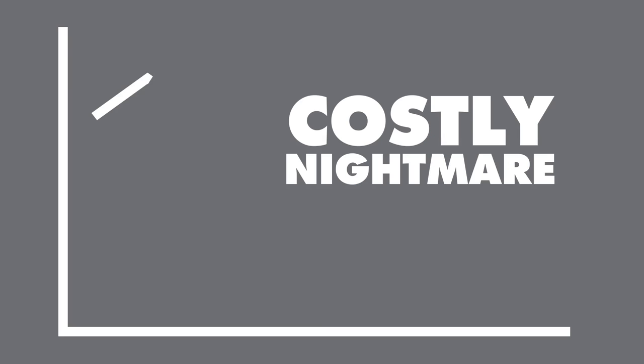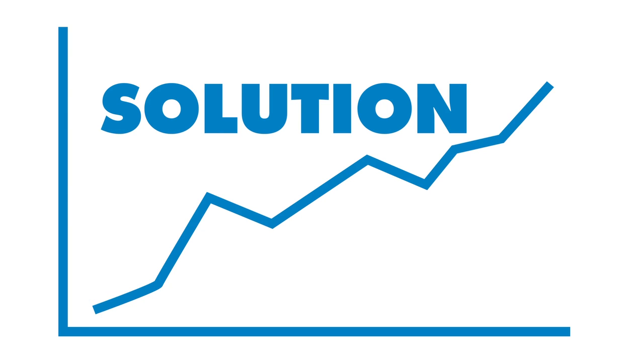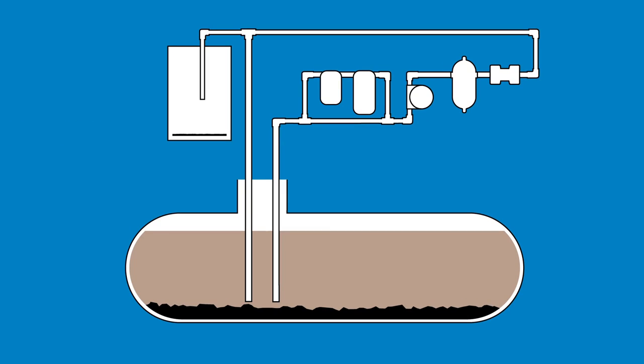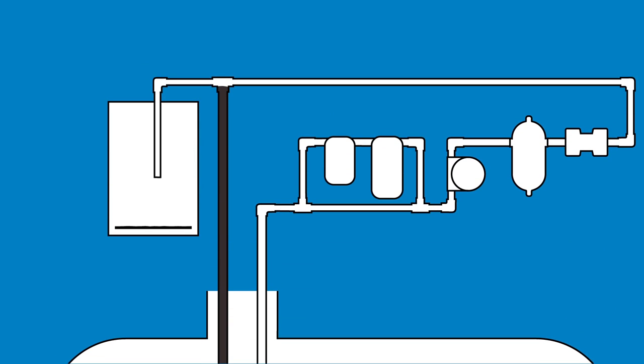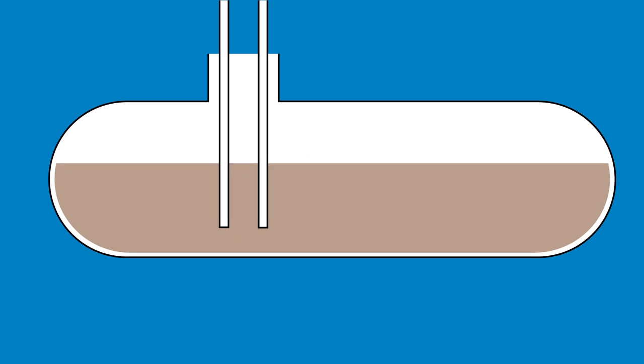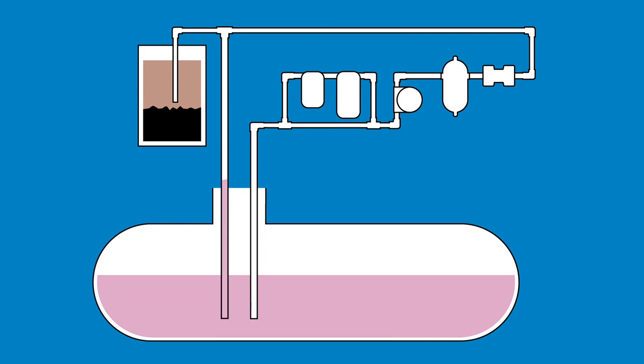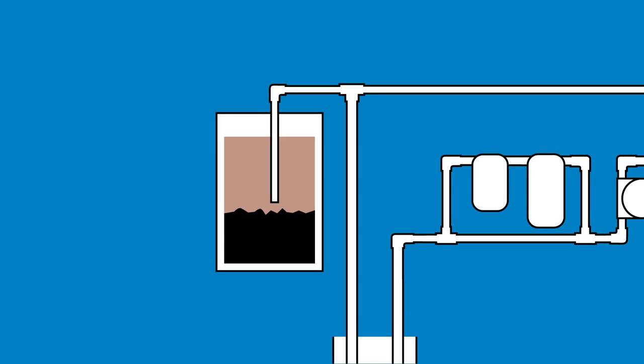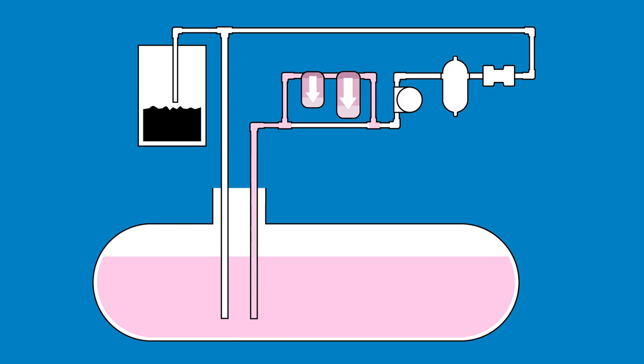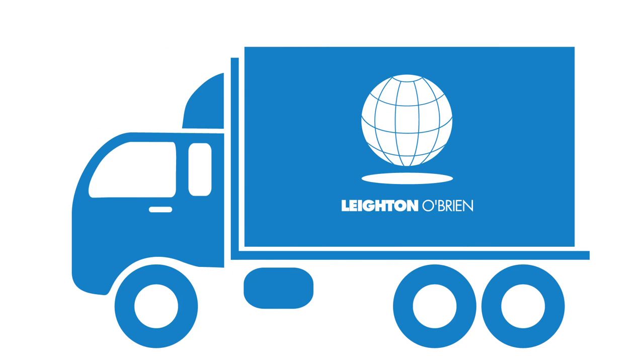Problems with dirty tanks and fuel quality can be a costly nightmare for your business. Leighton O'Brien provides a comprehensive solution for cleaning tanks and restoring fuel quality via a three-stage process. First, we remove water, sediment, and rust by traversing 100% of the tank floor and store this waste material in a settlement tank. The fuel is then circulated through clear hoses in a multi-faceted process including coalescing, fuel conditioning, and filtering, which removes emulsified water and small particulate matter down to 2 micron size. Finally, the remaining fuel in the holding tank is drawn off the top, treated, and returned to the tank — meaning only waste is removed and all your fuel is returned. Most tank systems can be cleaned in a single day, and all Leighton O'Brien tank cleaning services subscribe to the highest safety standards.